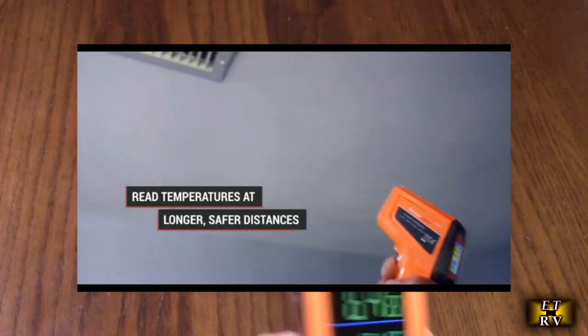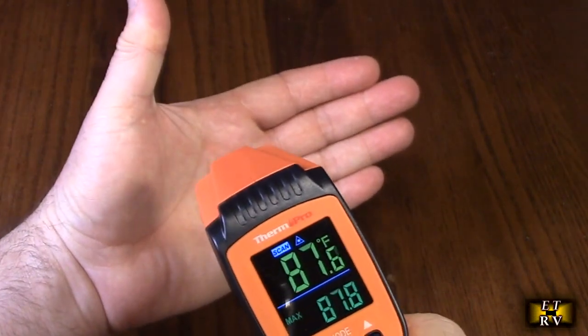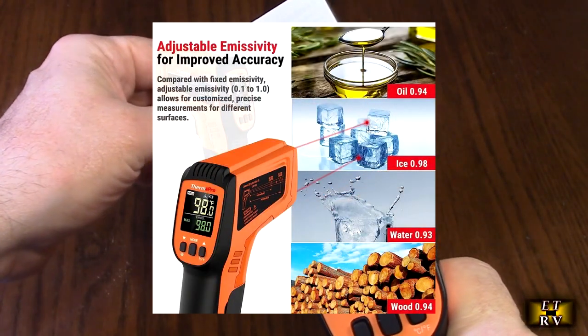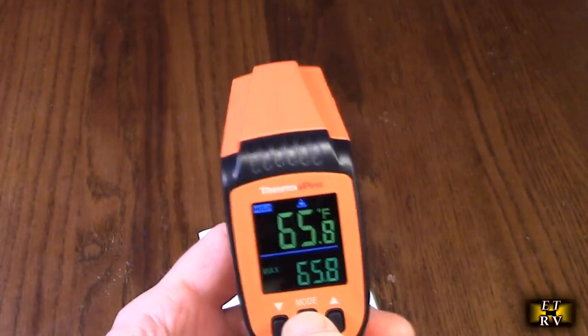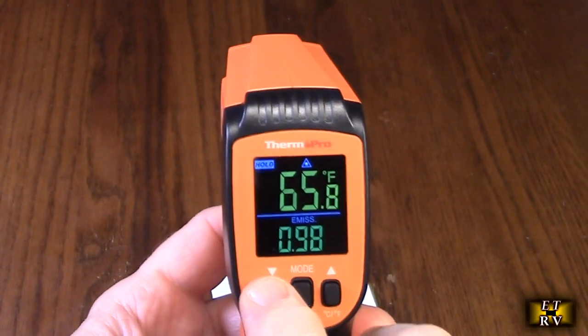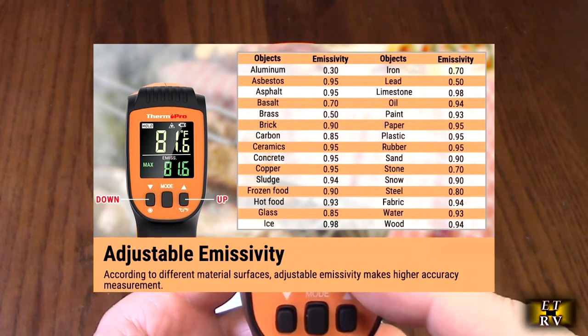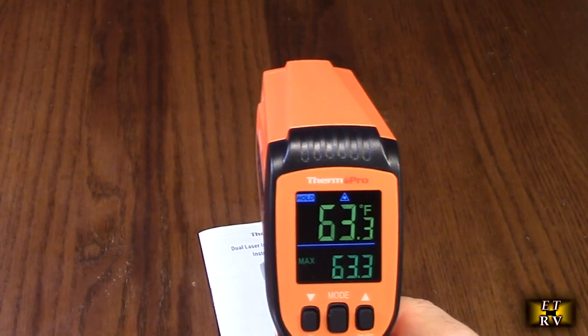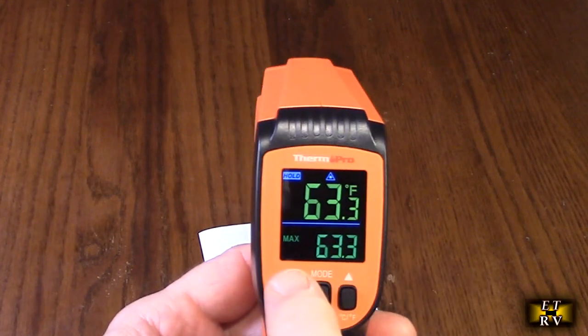The adjustable emissivity from 0.1 to 1 provides measuring accuracy across different surface types. Depending on what you're measuring — like a piece of wood on a table versus your hand — different surfaces reflect differently, and this allows you to adjust more accurately. If you hold the mode button down, you can see the emissivity setting and increase it. They have a nice table that shows how to adjust this, and it defaults to a certain number when you first use the unit.